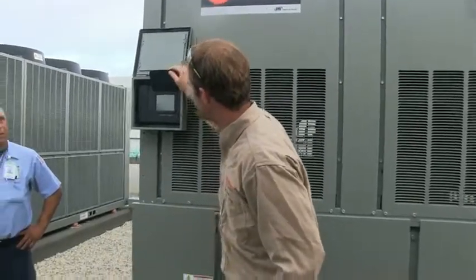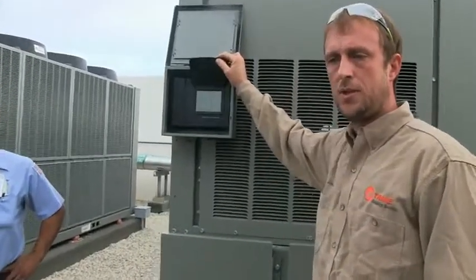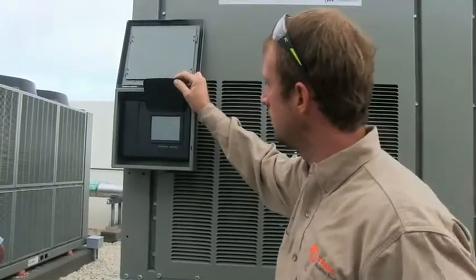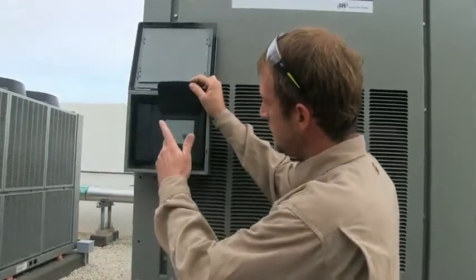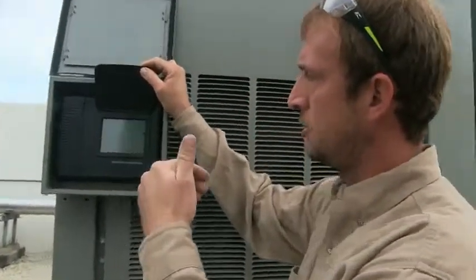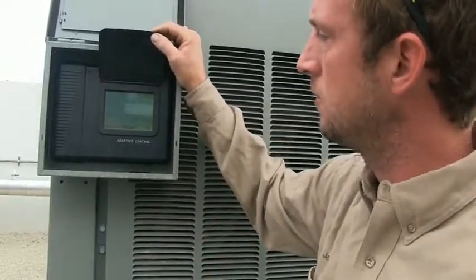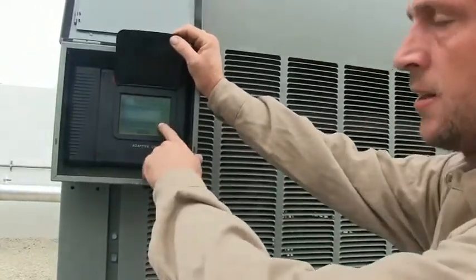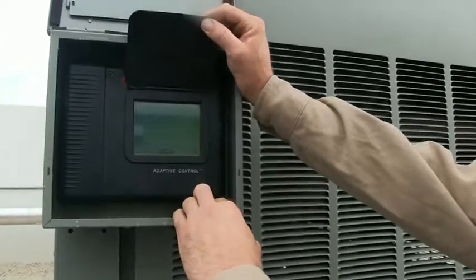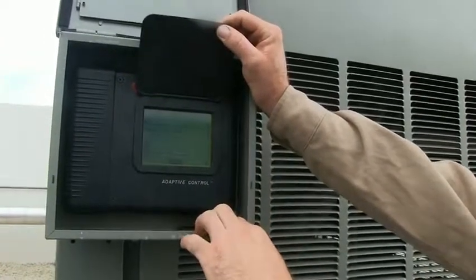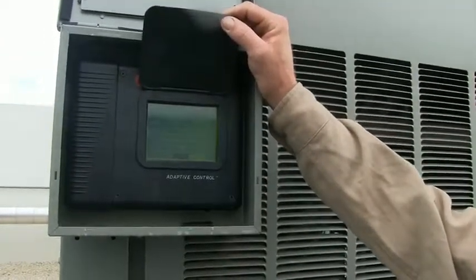The first menu you see is the main menu. That tells you the chiller operation mode. If you look up top, it says stopped. Below that, it'll show the operation for each circuit, circuit 1 and 2. It'll show you the entering and leaving chill water temps, the active chill water temp, and the demand current limit.